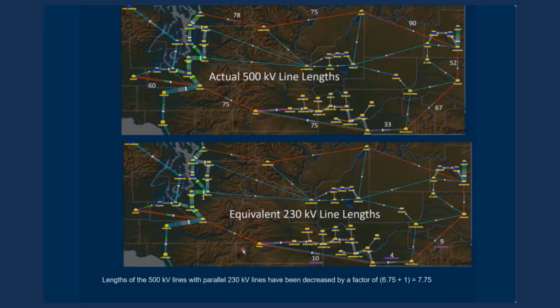So let's look at the cases where here we clearly have a 230 in parallel from Yakima to Findlay. We have a 230 in parallel from Findlay to Walla Walla. And we have almost a 230 in parallel because we've got this line that goes from Walla Walla to Coyote Ridge to Pullman. And it's almost in parallel, even though it's being routed through this station. So in this case, we'll do the reduction by dividing by 7.75. And we're taking the 75 and converting it to 10, the 33 to 4, and the 67 to 9.